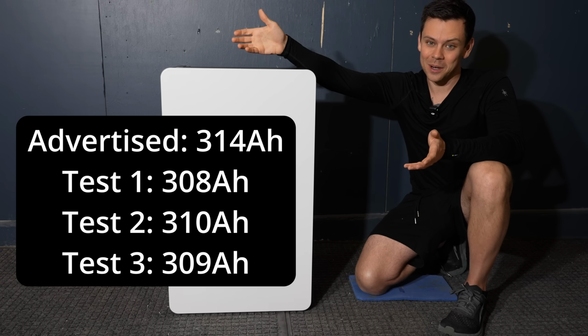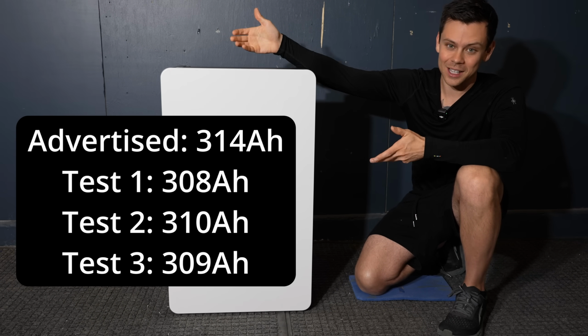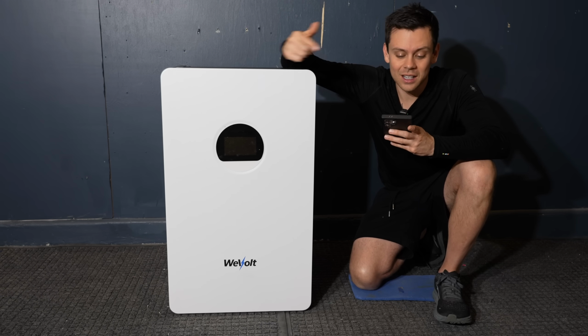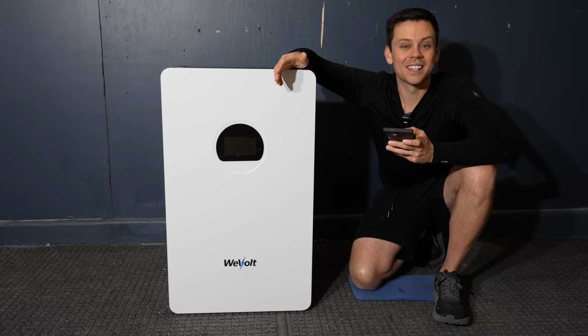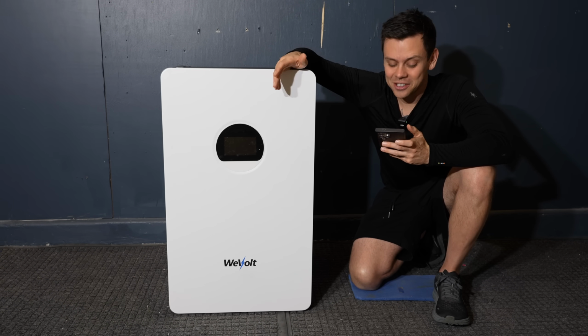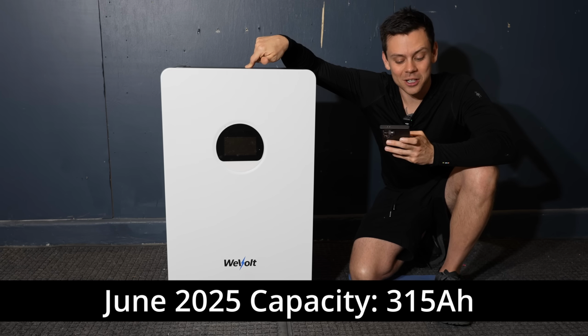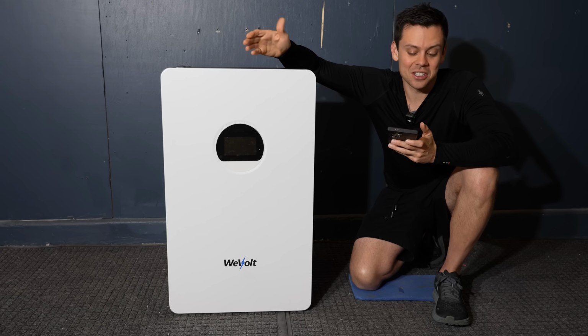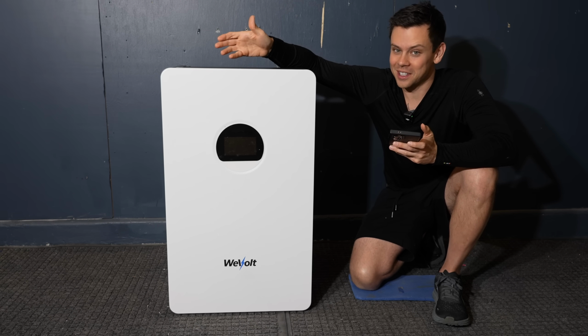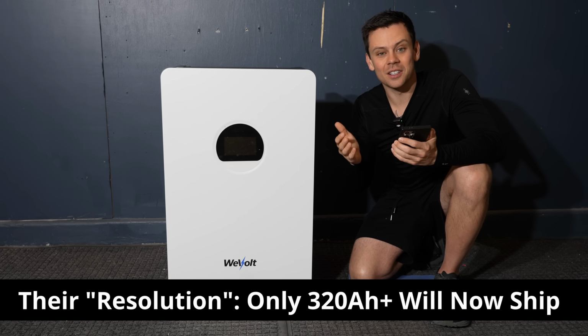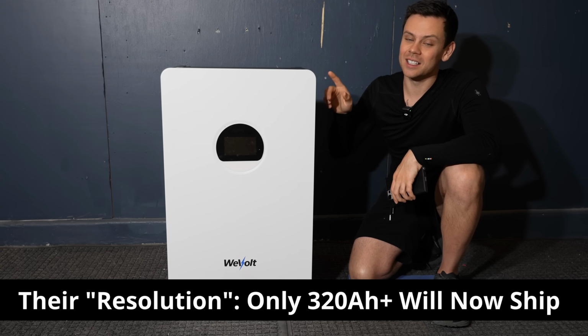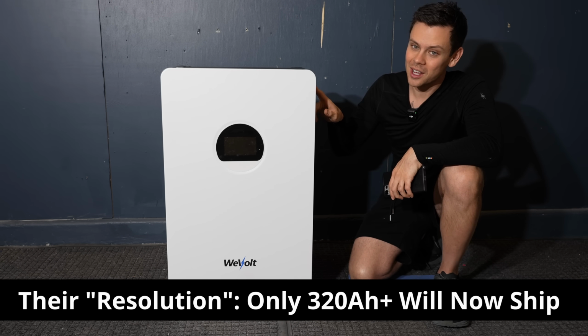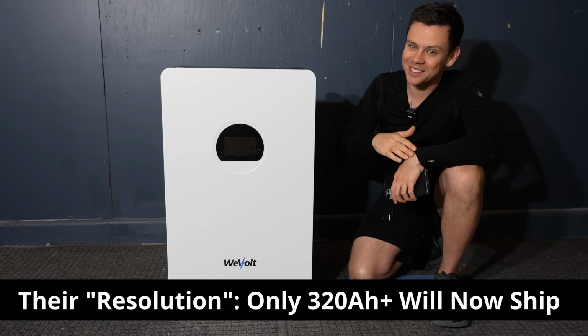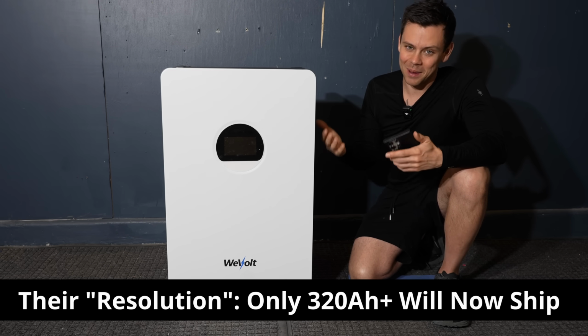So I asked the company why their battery is not passing the capacity test. They did an investigation and said it's calendar aging. They said this battery did 315 amp hours in June 2025 and it just naturally dropped to the figures I'm getting. But they say they won't ship batteries out unless it has at least 320 amp hours, so by the time it reaches the customer it will have the full capacity.